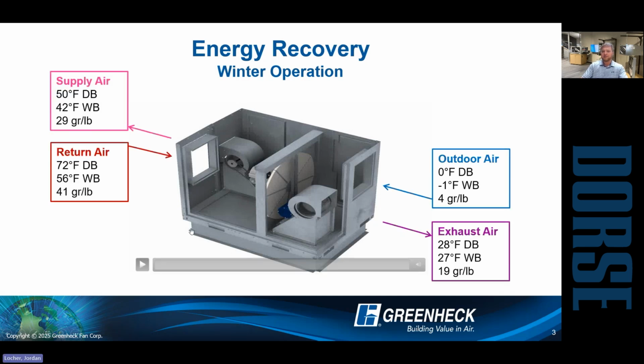In the wintertime, this is exactly opposite. Now the outside air is relatively cold and dry. The return air is warmer and more moist, relatively speaking. And we're going to transfer that heat and moisture and keep it within the space and prevent that cold, dry air from coming into the building. That can either be done with a wheel or a core.